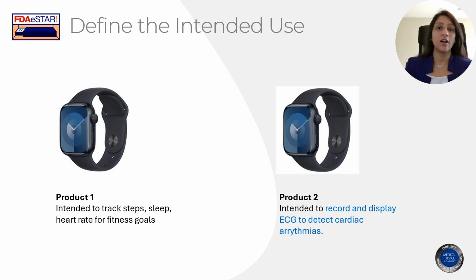Now that we saw FDA's framework on defining medical devices and categories, let's take a look at a case study on how to determine if a product is a medical device or not. As an example, I have used a wearable device, or a watch. In product 1, this watch is intended to track steps, sleep, and heart rate for fitness goals. Product number 2 is intended to record and display ECG to detect cardiac arrhythmias.